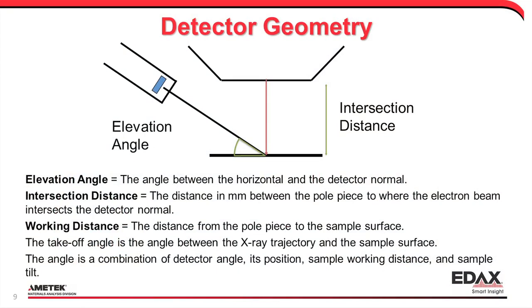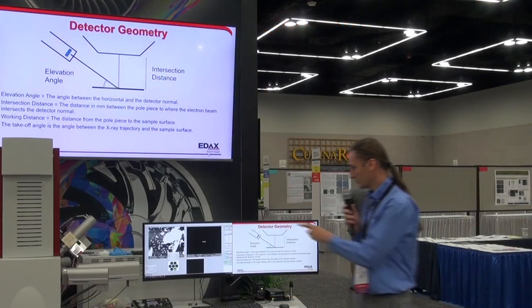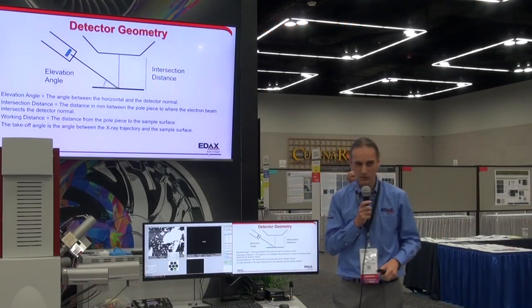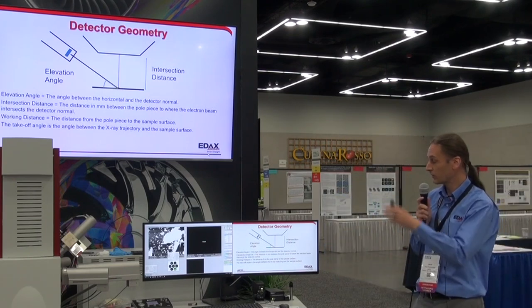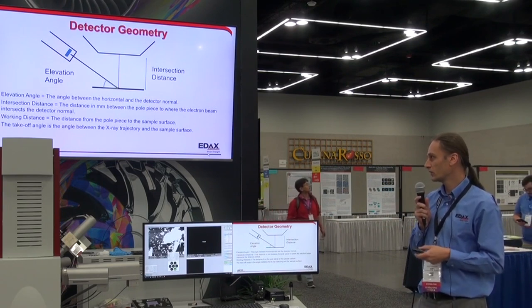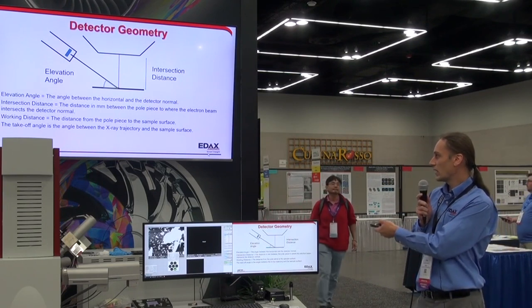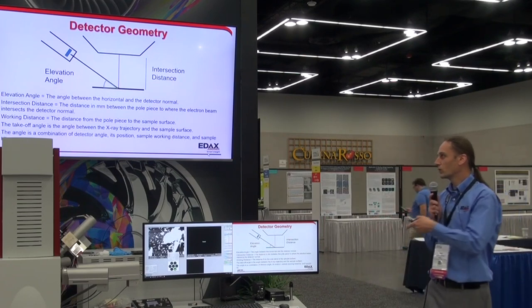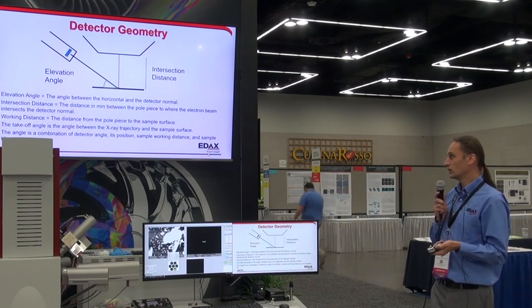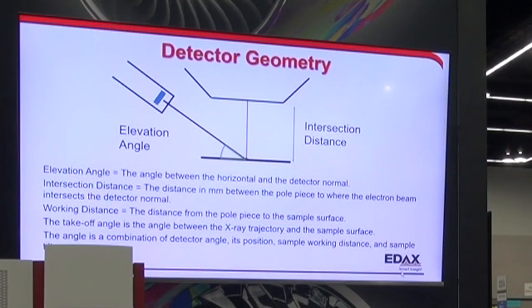The working distance doesn't have to match exactly, which we'll show in a moment. The intersection distance and elevation angles are fixed parameters once the detector is bolted onto the microscope. The working distance is the knob you can change freely to focus at different depths. The takeoff angle is the angle between x-ray trajectory and sample surface, and it depends on the detector elevation angle, where it's positioned, working distance, and the tilt.